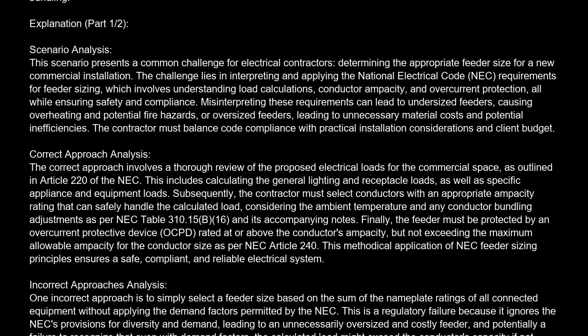Incorrect approaches analysis. One incorrect approach is to simply select a feeder size based on the sum of the nameplate ratings of all connected equipment, without applying the demand factors permitted by the NEC. This is a regulatory failure because it ignores the NEC's provisions for diversity and demand, leading to an unnecessarily oversized and costly feeder, and potentially a failure to recognize that, even with demand factors, the calculated load might exceed the conductor's capacity if not properly assessed.